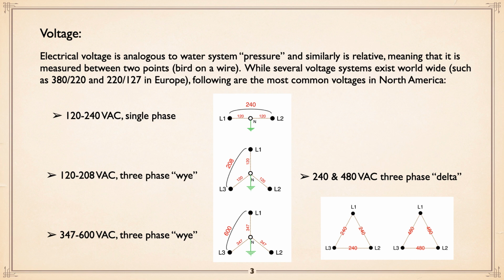So you can use the system in a residential area, giving them, instead of 240 AC, 208, but still 120 from any line to neutral. Or if you need to run a three-phase motor, you've got three-phase 208 volt AC.